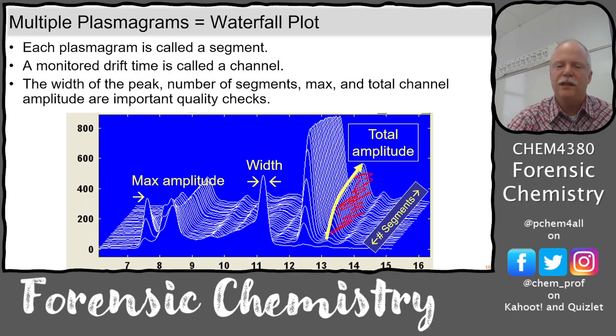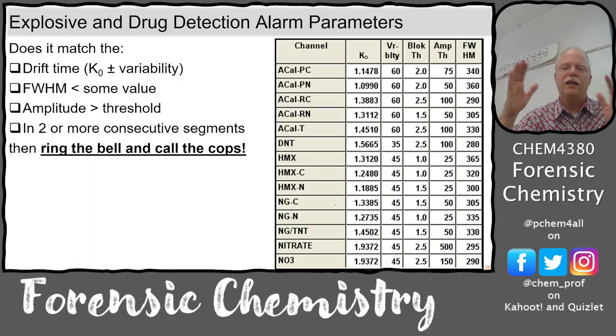We can put all of these into a data file inside the instrument, and you can see all these things. We have the drift time, which is this K0 number. So if the substance hits the detector and matches the drift time — like for dinitrotoluene, DNT, say 1.5 milliseconds plus or minus some small amount — that's a match.